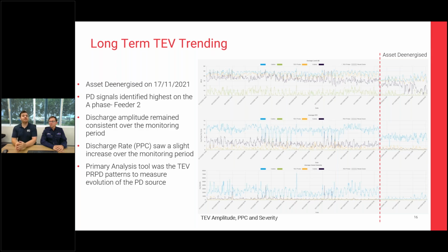One thing we did note over the entire monitoring period is that we didn't see a huge trend up or down in the amplitude of the signal. It remained very consistent, which was good, but also made it difficult to decide if it was getting better or worse. We did notice the discharge rate had a slight upward trend, but what we really used to analyze this was the phase resolved patterns.